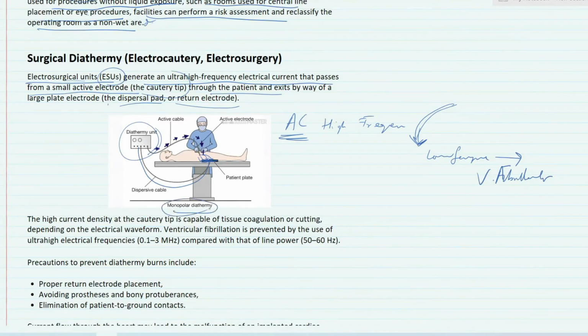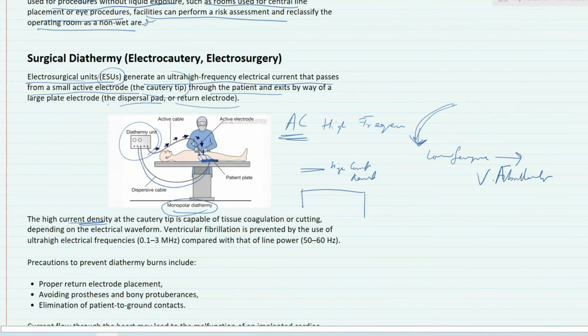This is a monopolar diathermy. What does monopolar diathermy mean? Monopolar means that the tip has a singular pole and the other pole lies here. Now, what is the reason the burning or the cutting is happening here and not at this place? Well, the reason is current density, right? The tip has high current density, and the plate has low current density.